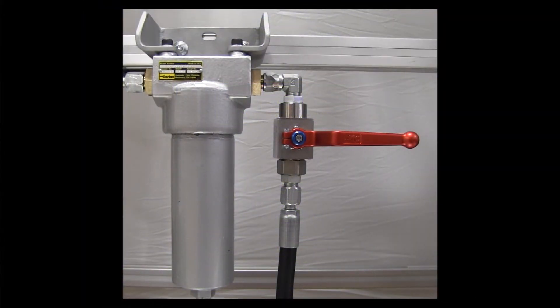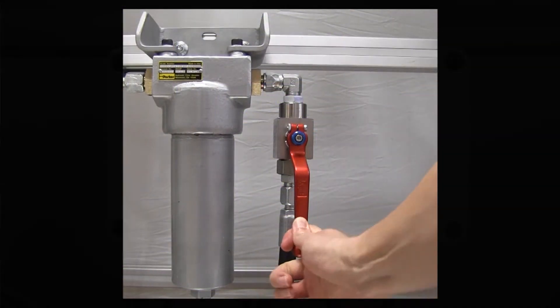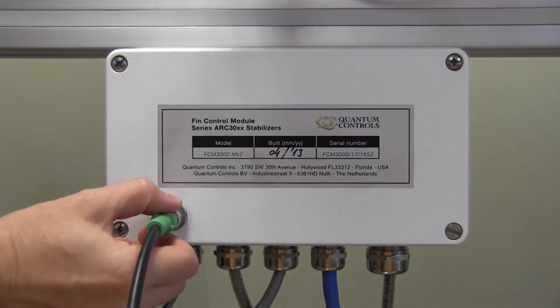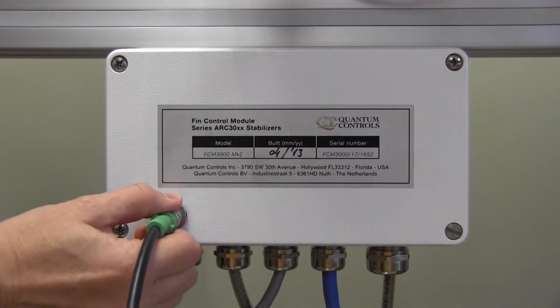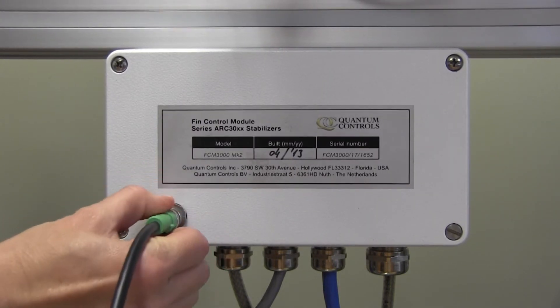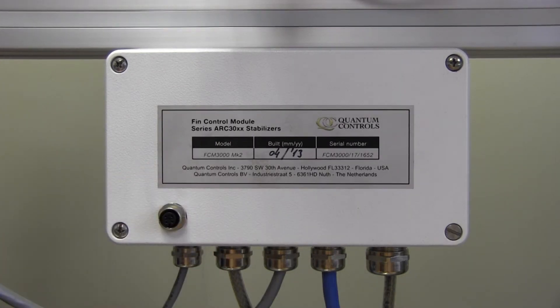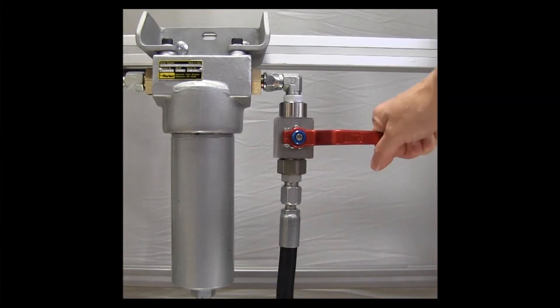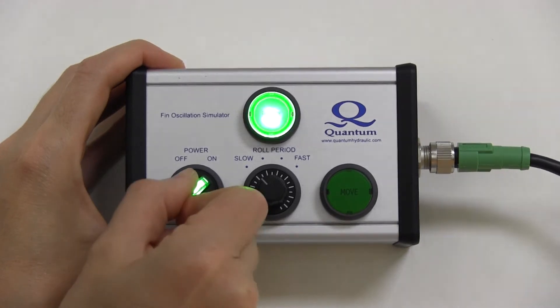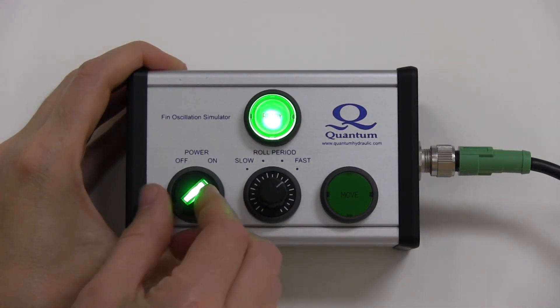Please note that if the hydraulic isolation valves are open when the FIN Oscillation Simulator is connected or powered on, a loud bang might be heard. This is a hydraulic hammer effect, which can be avoided by keeping the hydraulic isolation valves closed when the FIN Oscillation Simulator is connected, disconnected, or powered on or off.